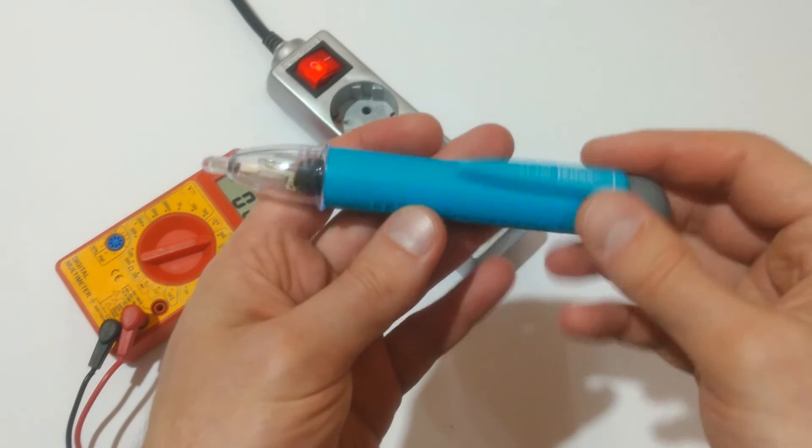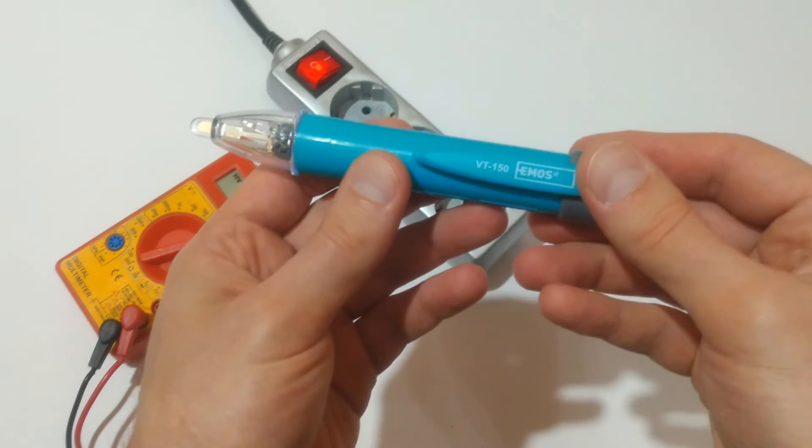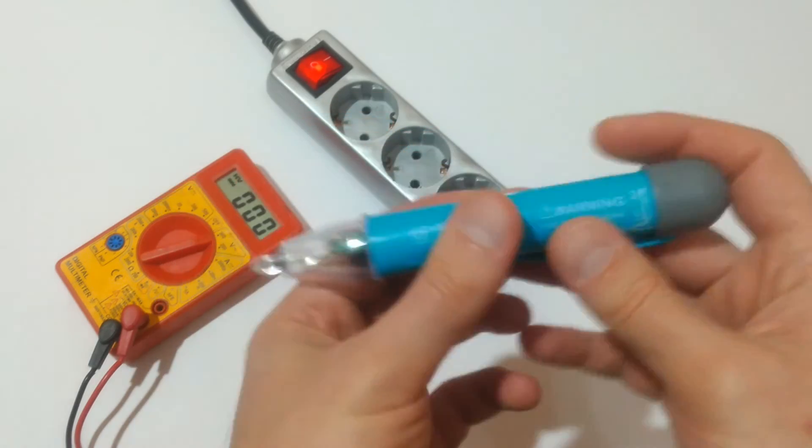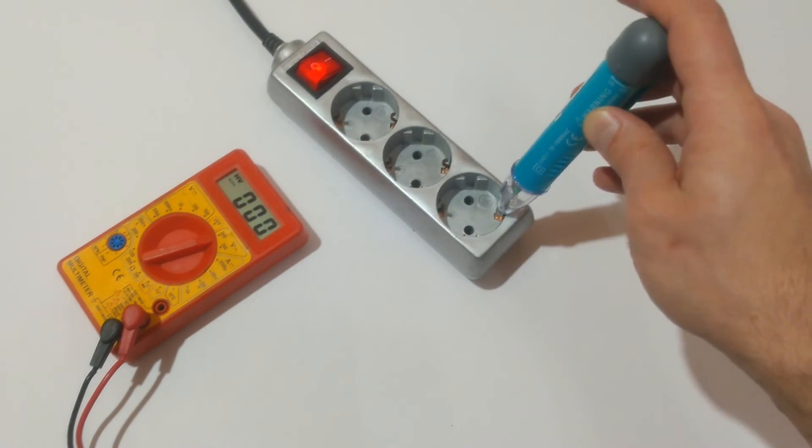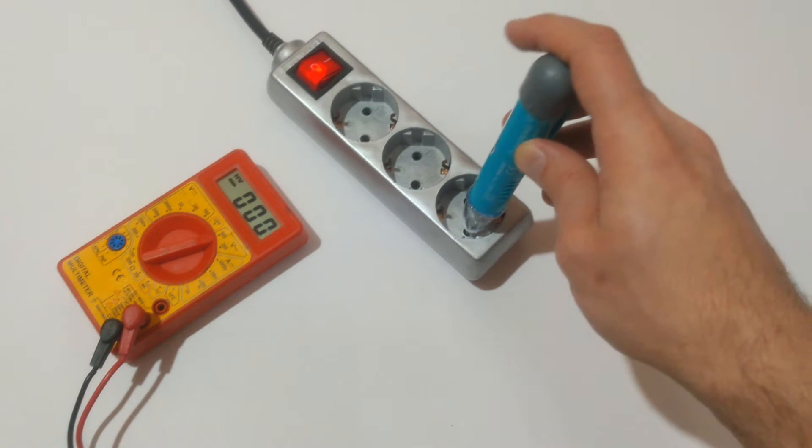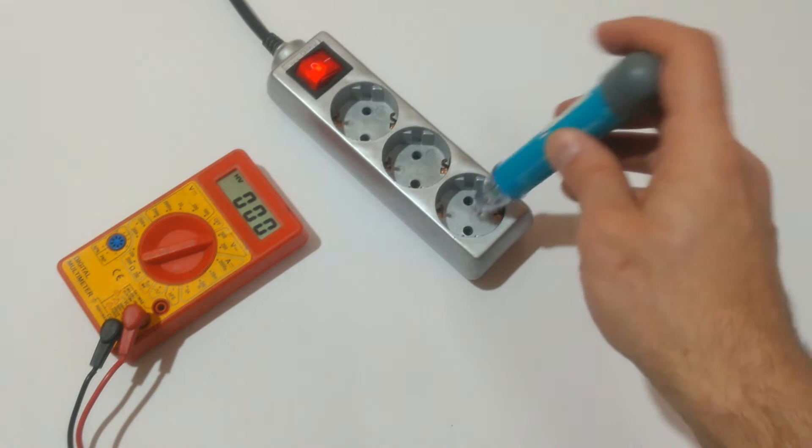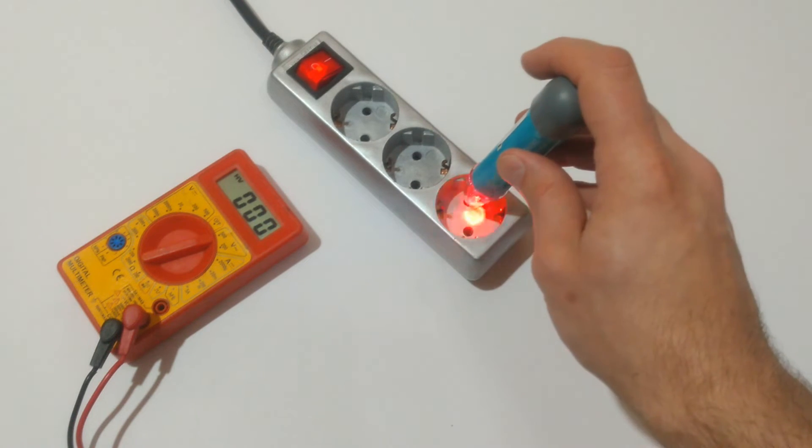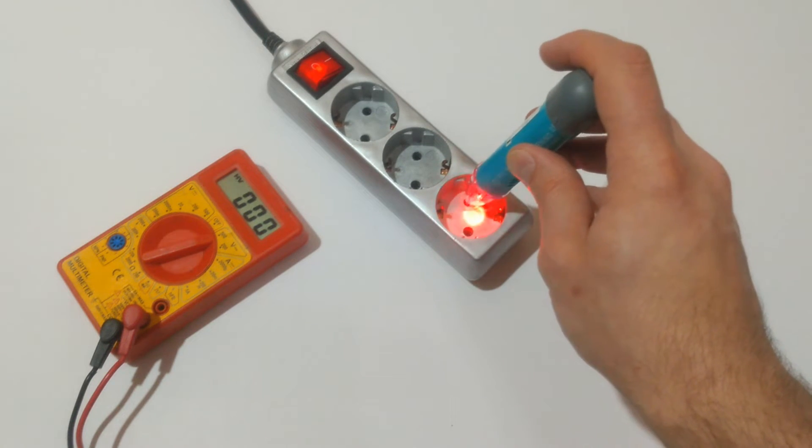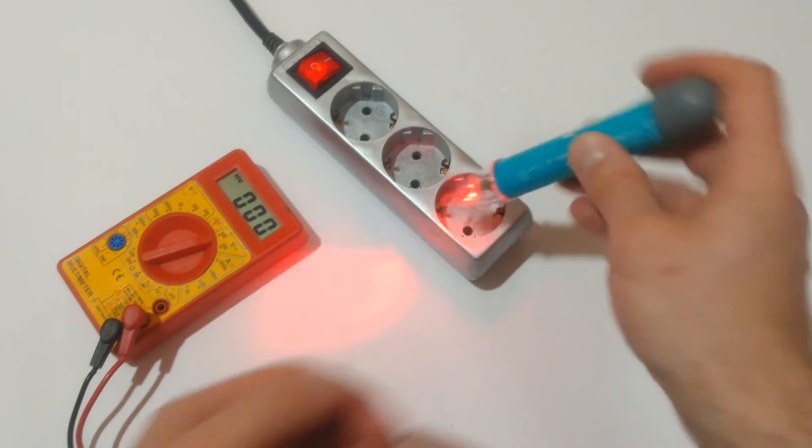And lastly EMOS. Nothing on grounding, nothing on the neutral, and beeping on the live.